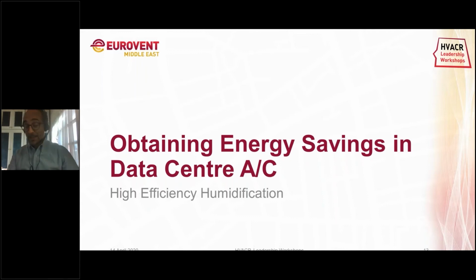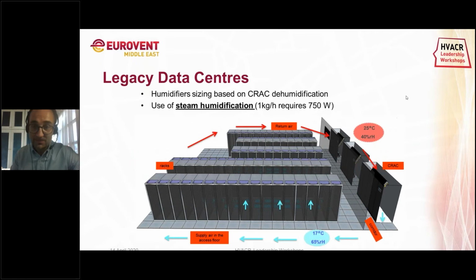This is a big debate. In certain areas of the world, they are trying to get completely rid of the humidifiers, and we can understand the reason. Let me show you an example. This is a legacy data center. It's a bank, so with a typical low temperature design, room-based air conditioning, 25–40% on the return, 17 degrees on the supply. These type of systems are out there a lot.